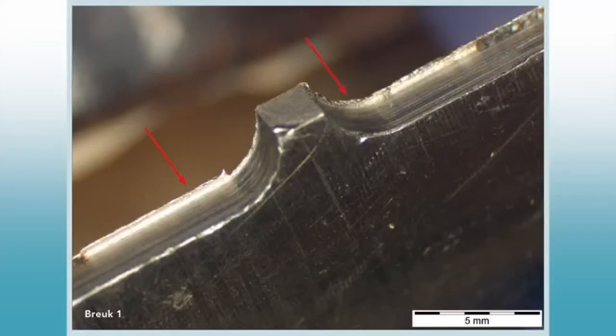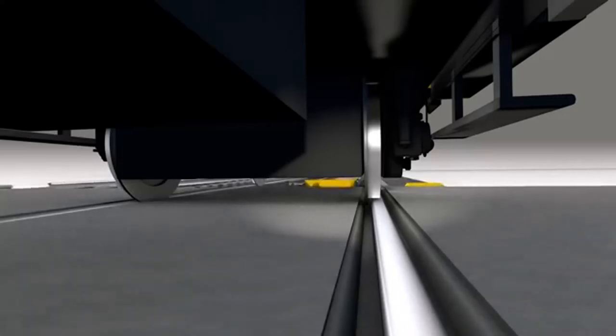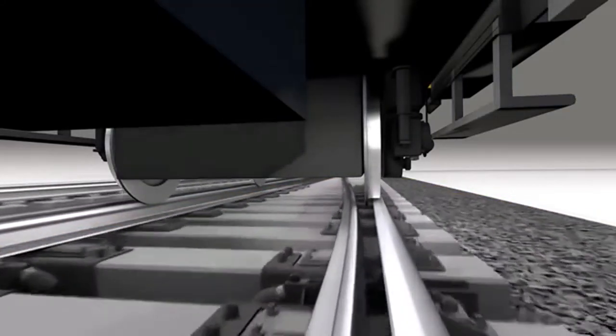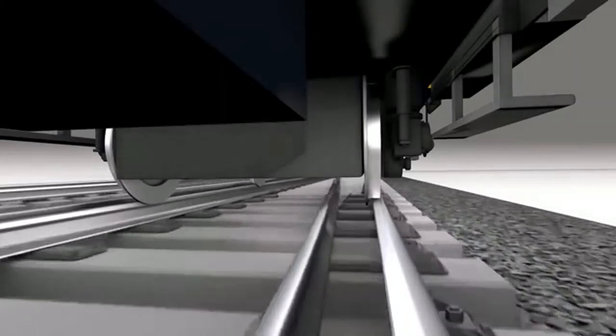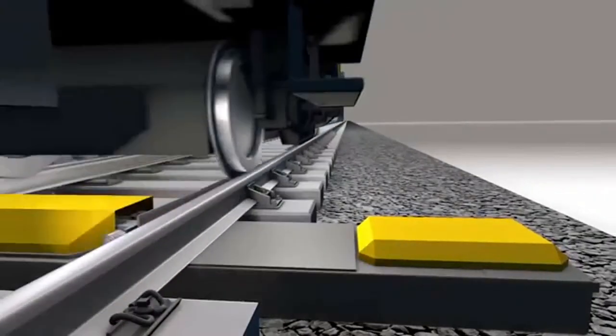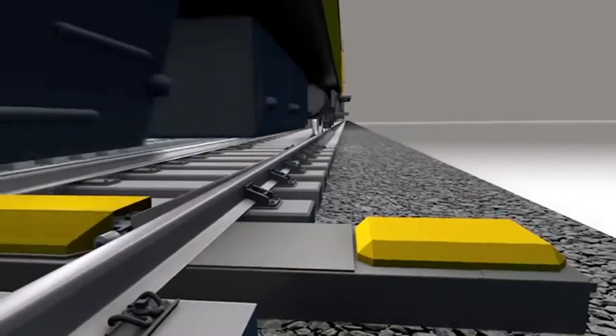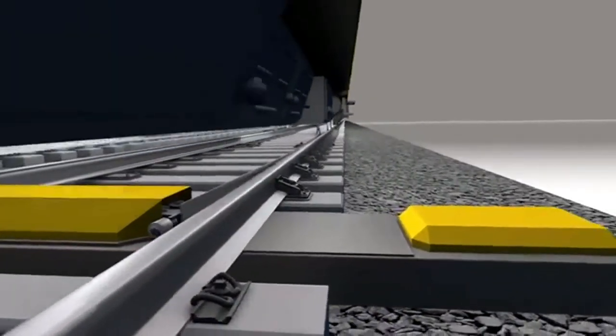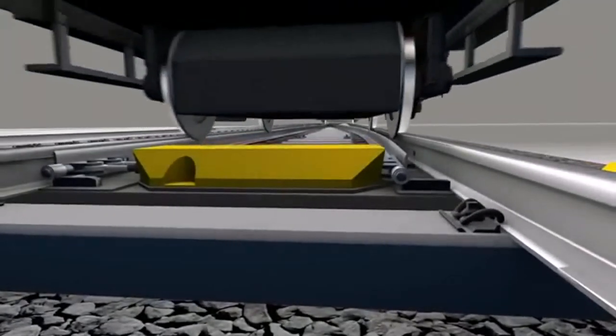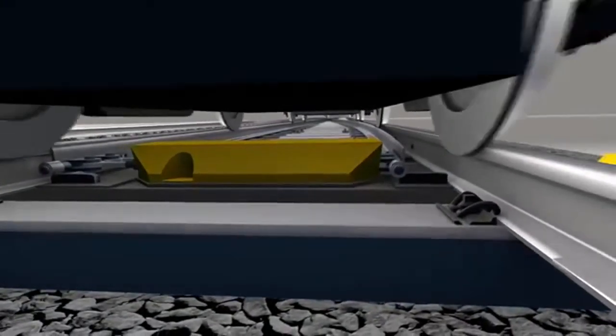First of all, the ring revealed finishing defects, making the ring more susceptible to fatigue. Furthermore, the fatigue fracture arose because, over a long period of time, the ring was exposed to additional forces coming from passing trains hitting the switchblades with their wheels. This hitting action caused the switchblade to oscillate, thereby applying additional forces to the point machine and to the ring, for which it was not designed.